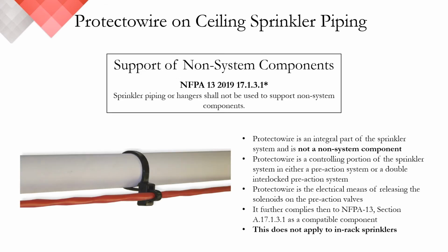The challenge with a webinar is not being able to see your crowd. I'm sure there are a few of you out there looking at the NFPA 13 reference and the photo of Protectowire with a double loop pipe strap on a sprinkler pipe and you're shaking your head. The interpretation of NFPA 13's clause about non-system components must not be misinterpreted. When Protectowire is employed in a pre-action or double interlocked pre-action system, it becomes a critical component and the controlling portion of a sprinkler system, as it has the ability to electrically release solenoids on valves.